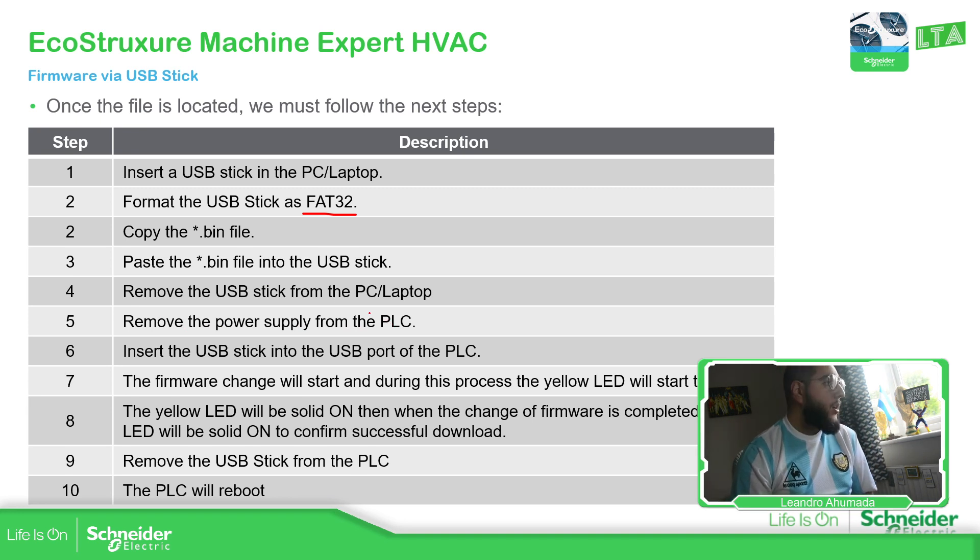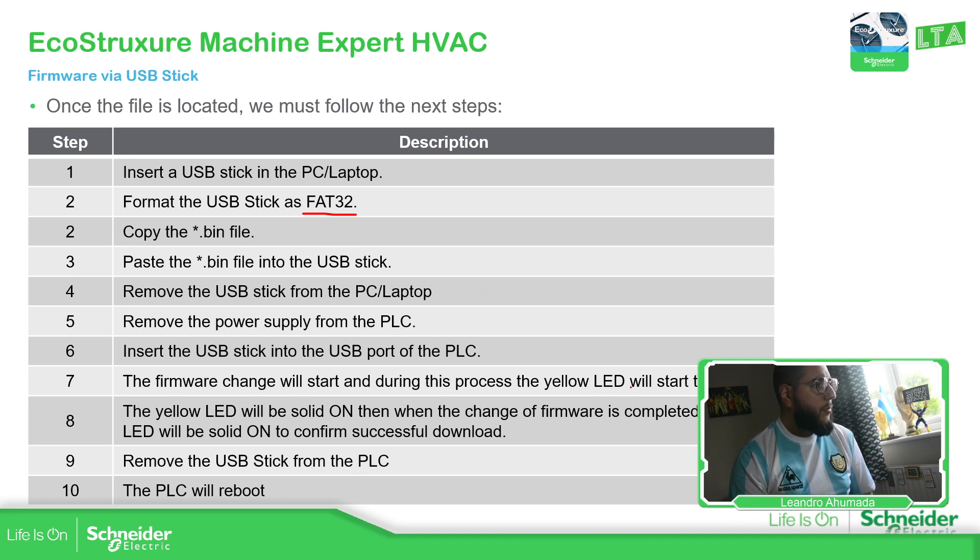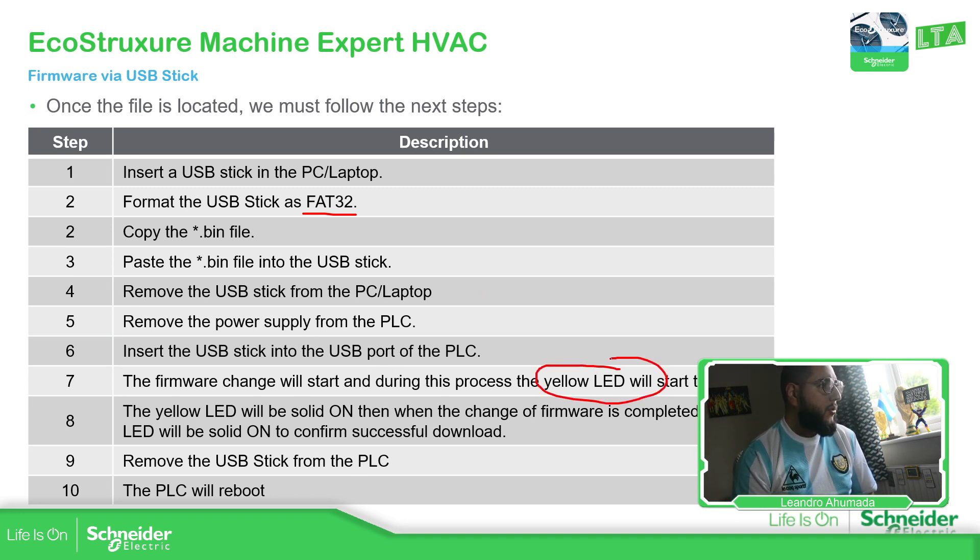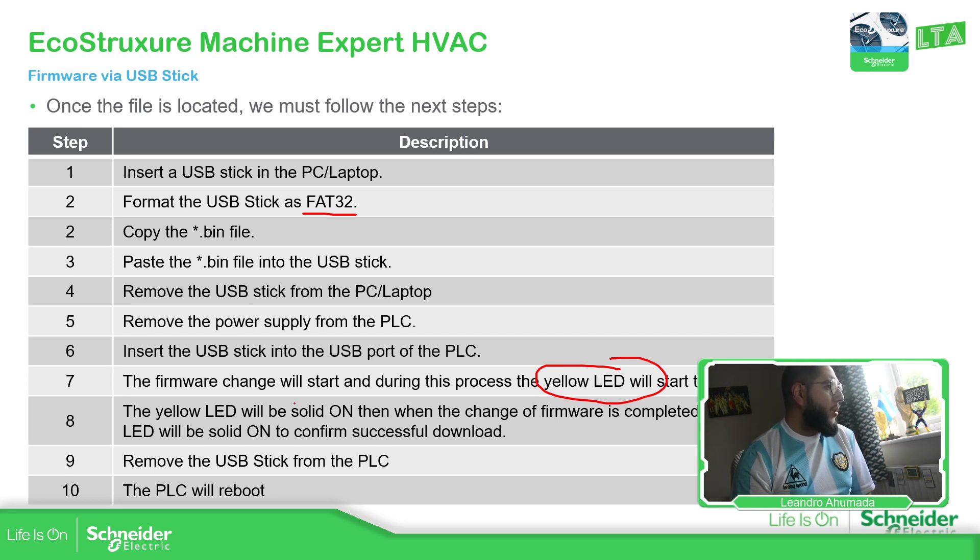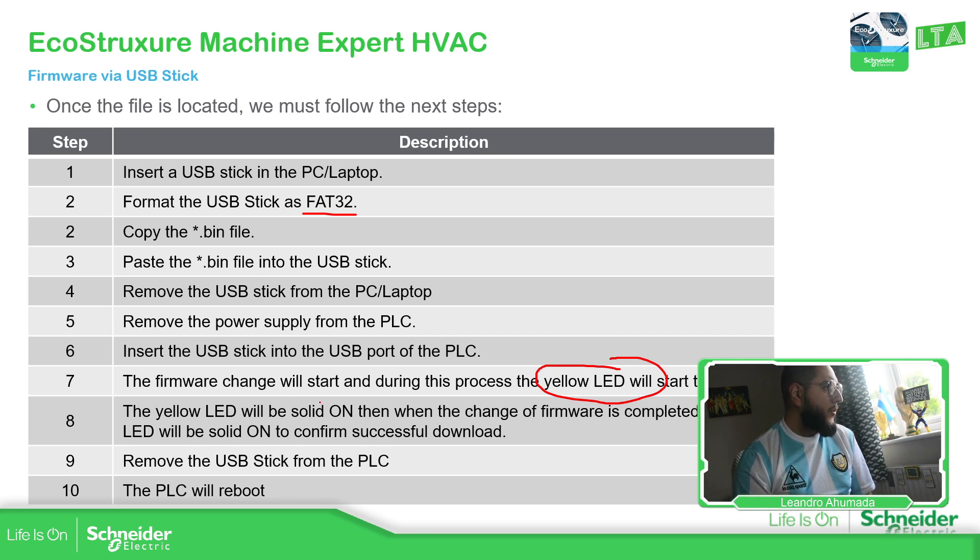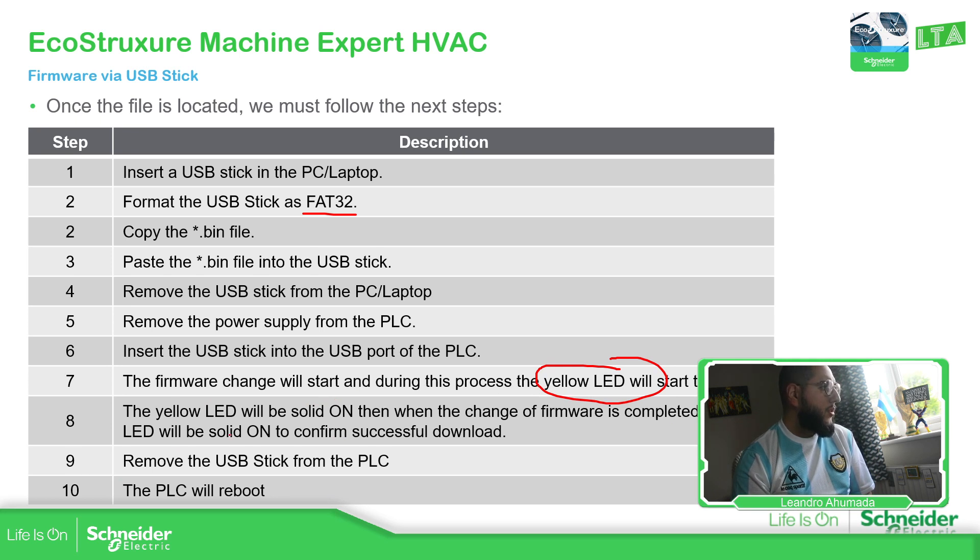Now what we need to do is remove the power supply from the PLC and put the USB. Once that is started, we just wait during the process. You will see the yellow LED, so it means that it's changing information. And then when it's solid, it means that the firmware is complete. And once the LED is green, we just remove it.